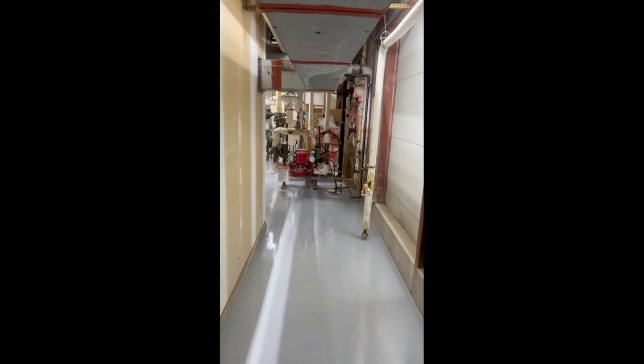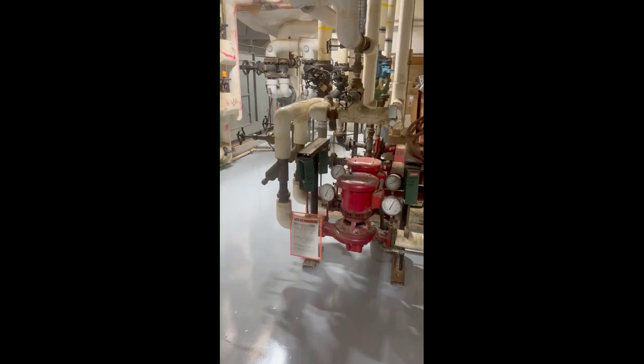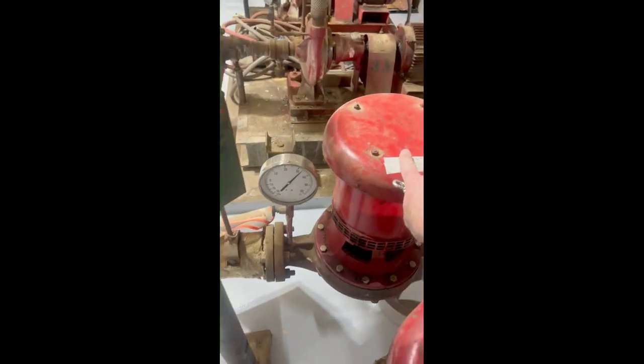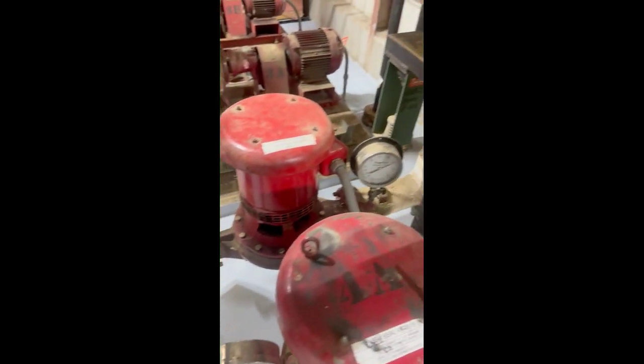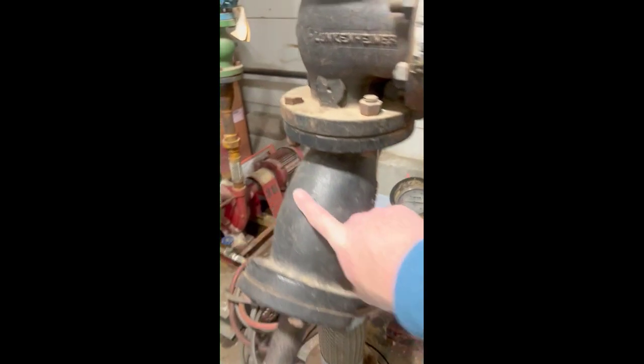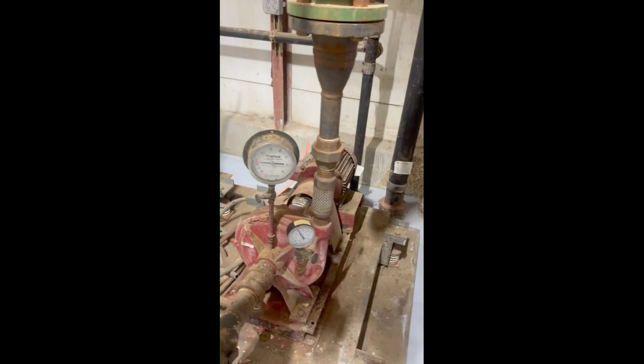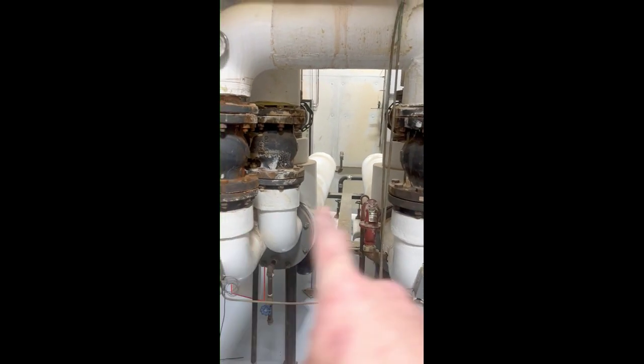Okay. As I continue to look around, I don't see anything earth-shattering, nothing cause for concern. But I am going to look at my pumps. So 4B is running. It's got good head pressure. I don't see any leaks. This pump is running. It's 3A. My hot water bundles and my heat exchangers are actually exchanging heat. And that's what these two things do.